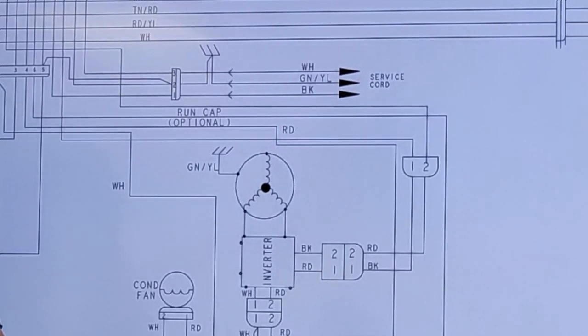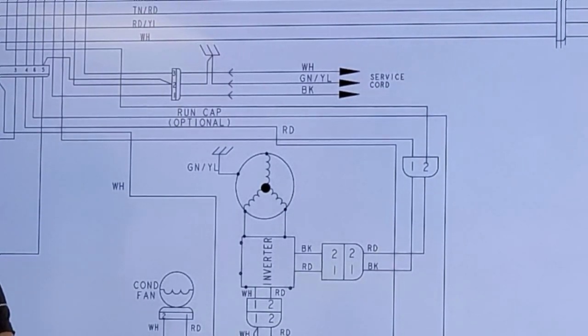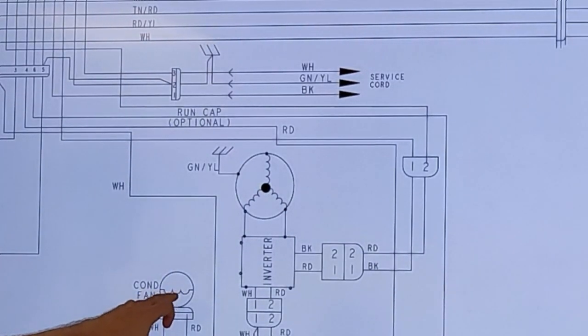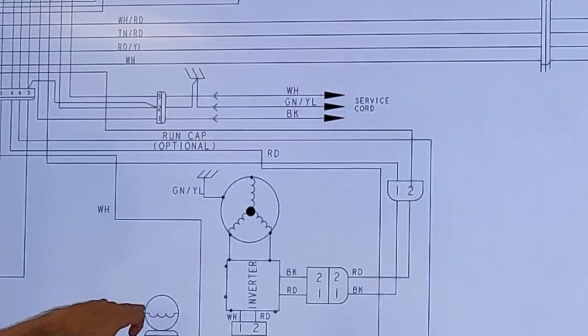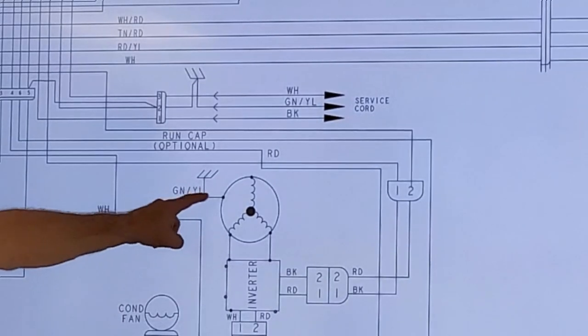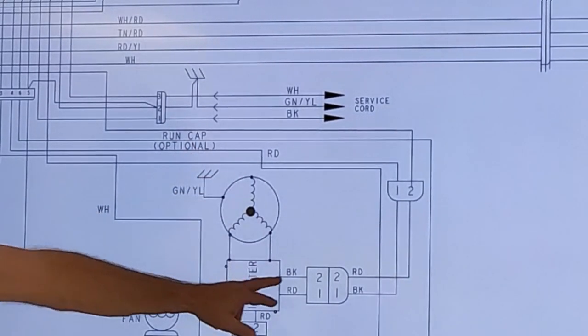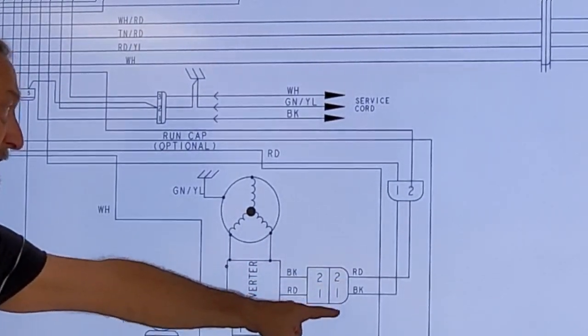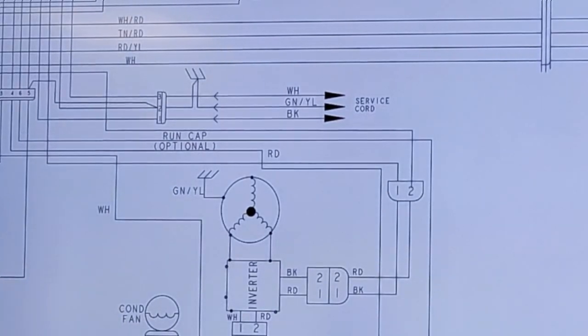You'd see this plug that had a pink and a tan wire on it — they call it brown now but it's usually tan. It had a pink and a tan wire and the plug was just laying in there. You always wondered what the plug was for but it was never connected to anything. Well, that is a test terminal. So when you go into defrost, normally if the thermostat was open, you couldn't see if the heater was working or not. So when you go with a mechanical advance of the timer, you could jump it out here and that would apply voltage.